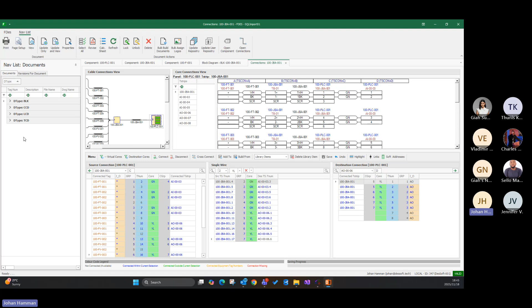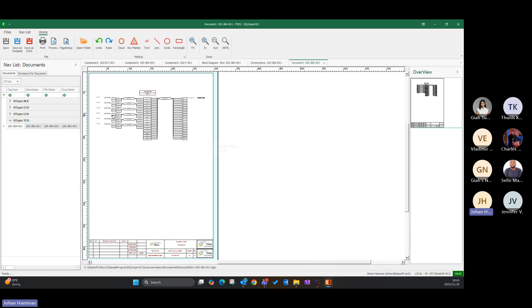So now you will see suddenly I've got a termination connection diagram for the JB. If I open this, it created this drawing from that information. As you see, I didn't draw any lines, but there's my JB, the 3 flow transmitters, then the valves. And here also the detailed information where this cable is connected on the right-hand side to this terminal strip and terminal number, and the left-hand side to that terminal strip and terminal number. All of that has been marked for me already, and this drawing is ready.